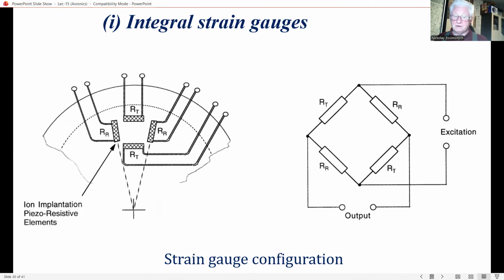The output of the bridge is proportional to both pressure and temperature, as the modulus of elasticity of silicon is temperature dependent. A temperature-sensitive resistive element is therefore incorporated into the diaphragm to measure the temperature, so that the temperature-dependent error can be corrected in the subsequent processing of the sensor output. These temperature-dependent errors are very stable and repeatable.